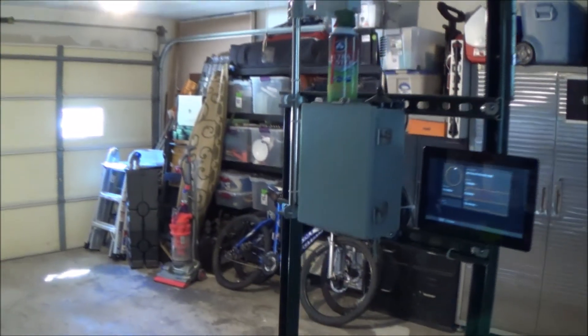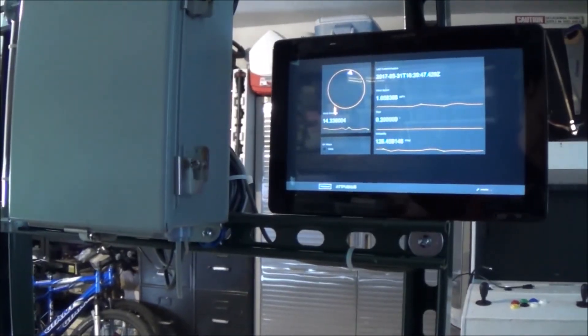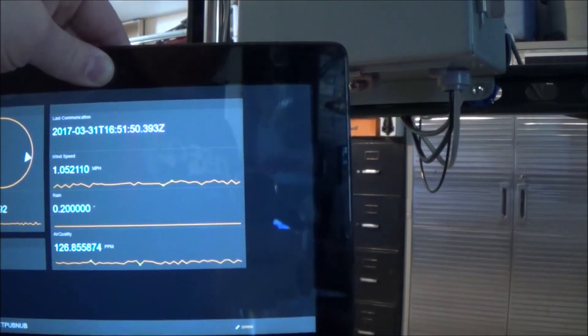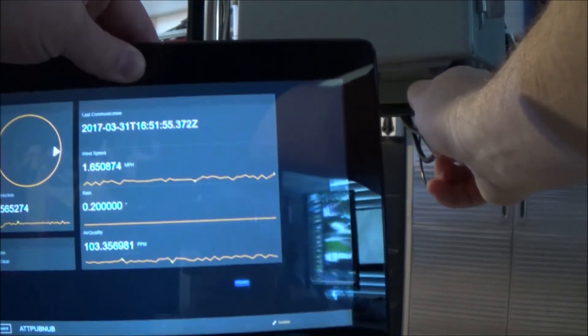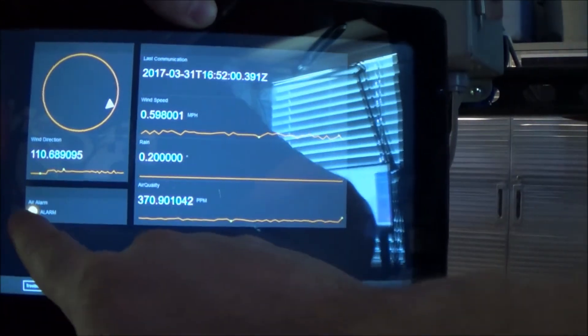Since it's hard to see screens outside in broad daylight, I'm going to do a little demo in here in the relative darkness. Keep an eye on air quality — I'm going to give it a shot of butane. See how it likes it. That shot up pretty quickly. You can see our alarm came on.